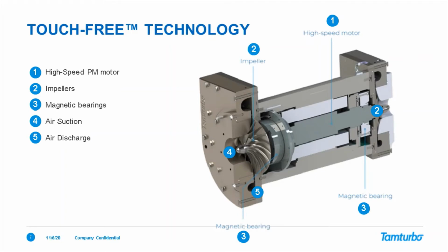Okay, thank you. So the touch-free technology is centered around a high-speed electric motor, which is there in the middle. It's a permanent magnet electric motor, pretty much similar to the induction electric motor in its working principle. The gray part in the middle is the rotor, and that rotates typically up to 35,000 RPM. And directly at the end of that spinning rotor are the turbo impellers, number 2 on the picture. In this cutout picture, we have an impeller on both ends of this one motor, and the impeller is sucking air in where there is the number 4, and then giving it a high speed, and this high speed then is turned into pressure in the volute in number 5.